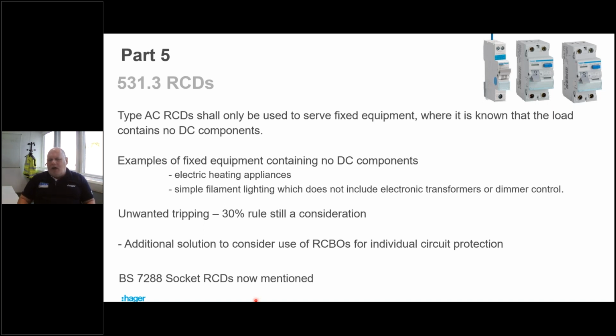BS 7288 socket RCDs. So we've got a socket with an integral RCD built in. It never had a mention in the regs book before. They weren't considered as additional protection. They do get a mention now. So where we're trying to adhere to this unwanted tripping 30% rule, we could possibly use those in an office, where we've got a lot of computer equipment.